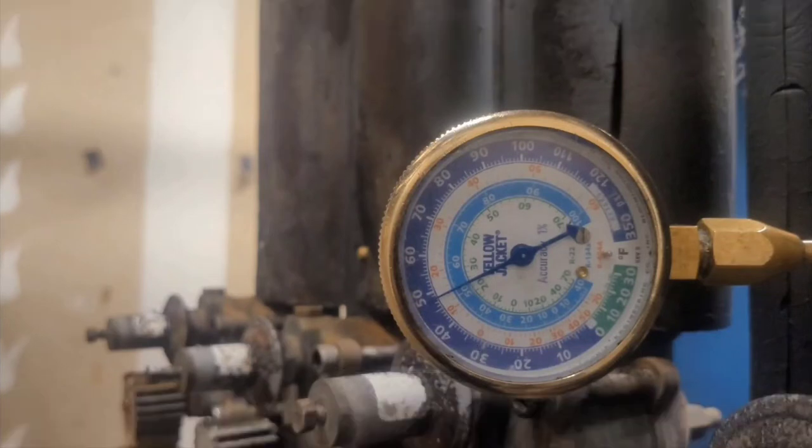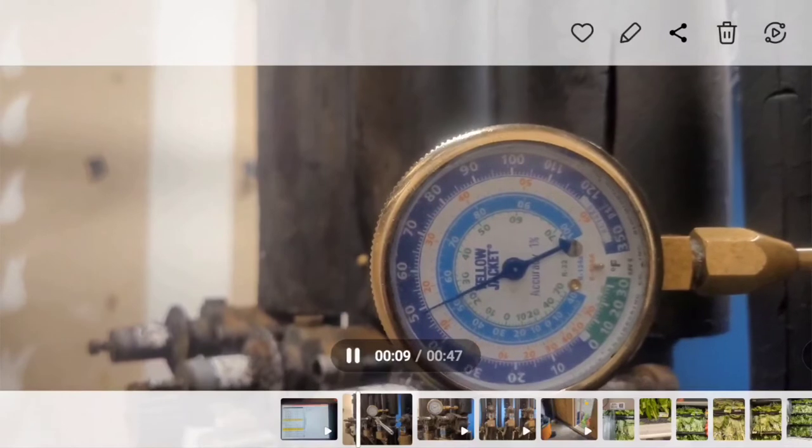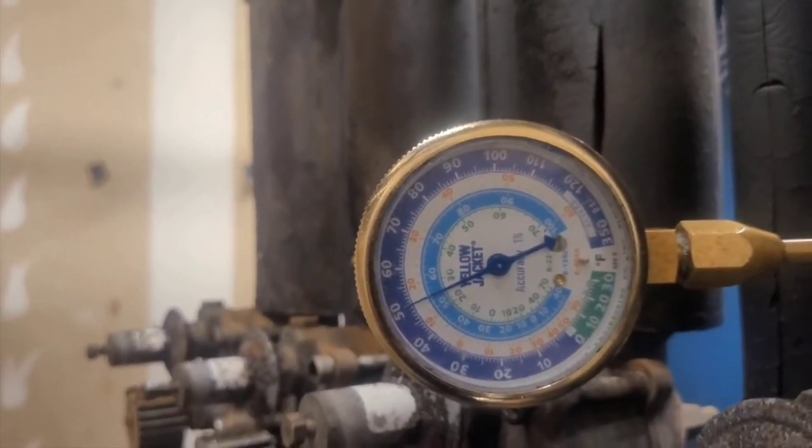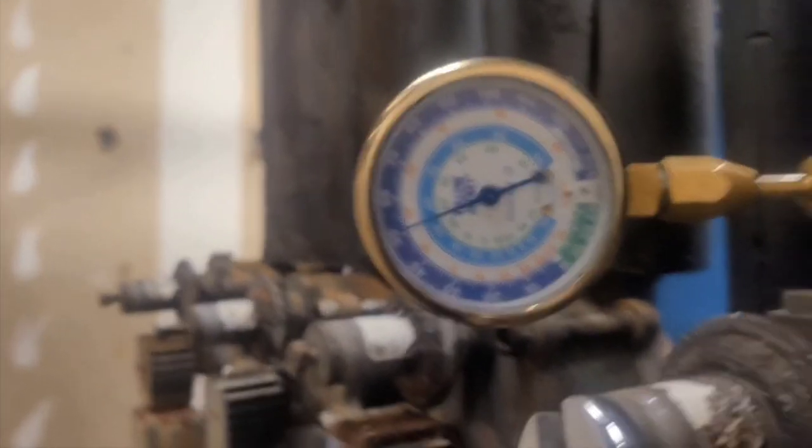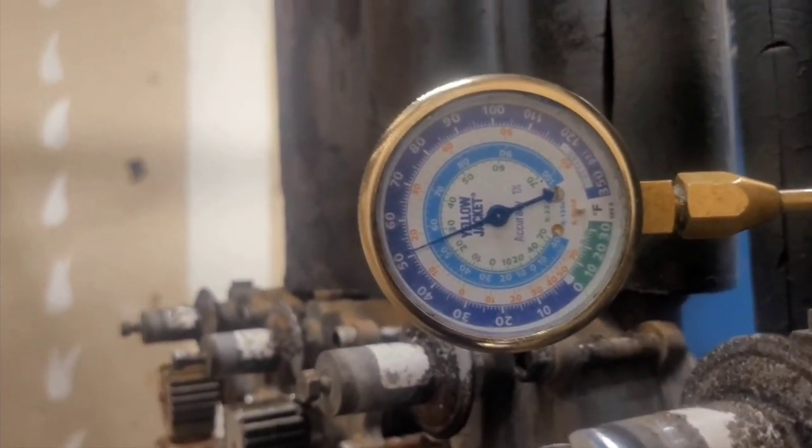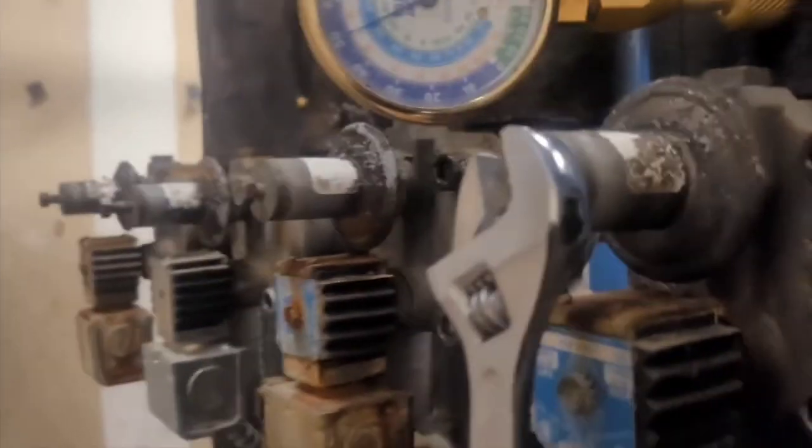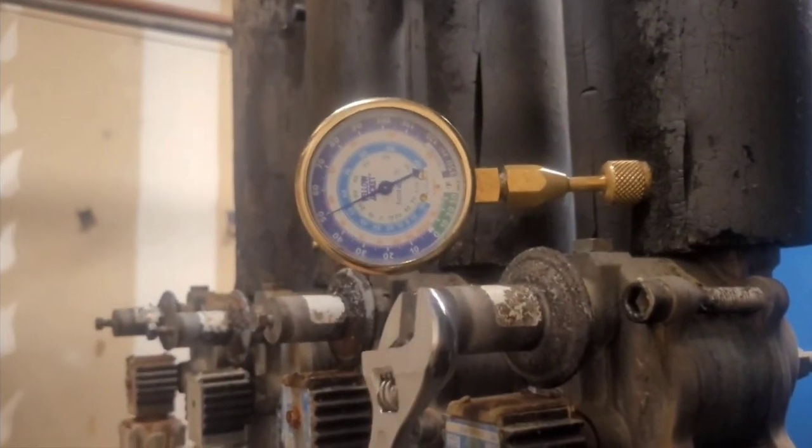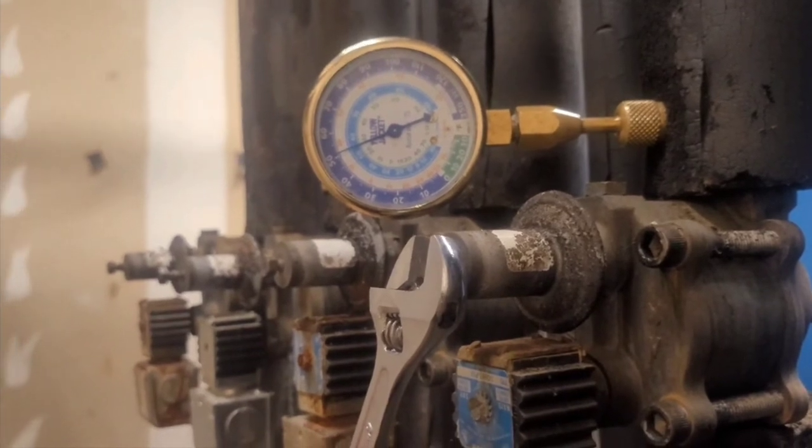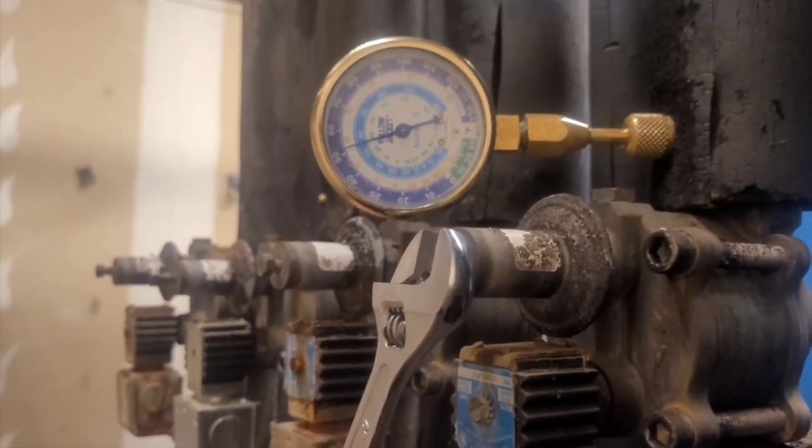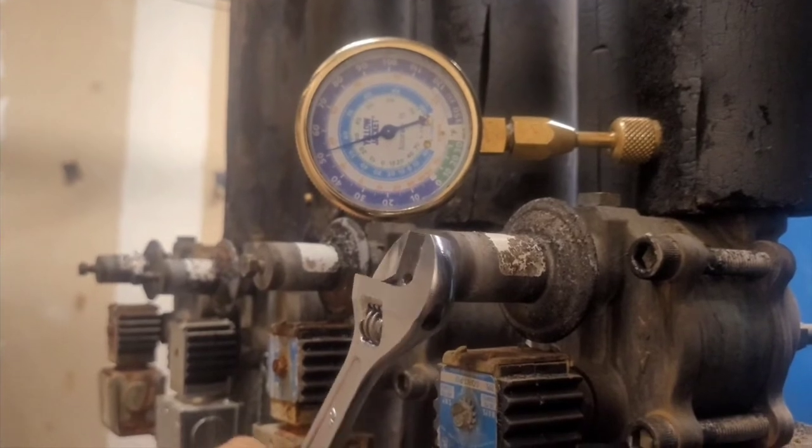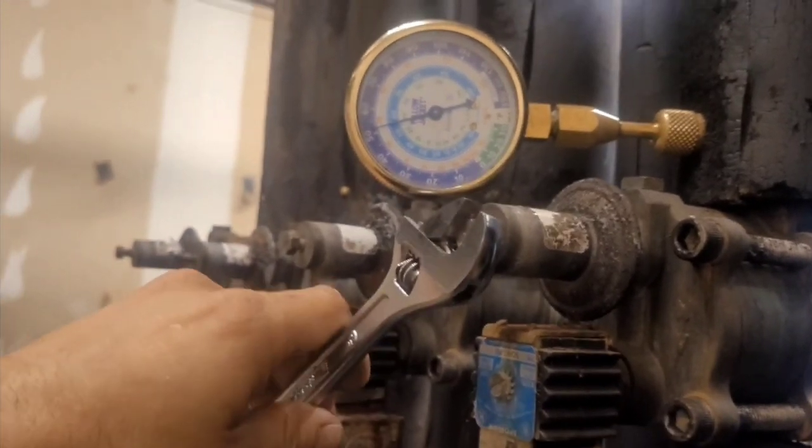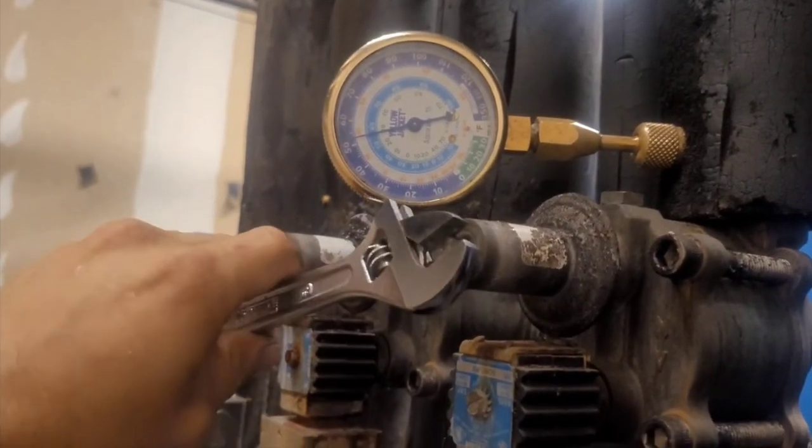So I turned it clockwise and it's about to go up. As you adjust it more, it goes up some more. You got to rotate it clockwise for the pressure on the inlet side to go up. You only got to do it a little bit too. If you go a lot, you'll see the needle move as you turn it. See as I turn it clockwise right there, it just goes up. So I set it at about 55, and then I went back around to the front of the rack.